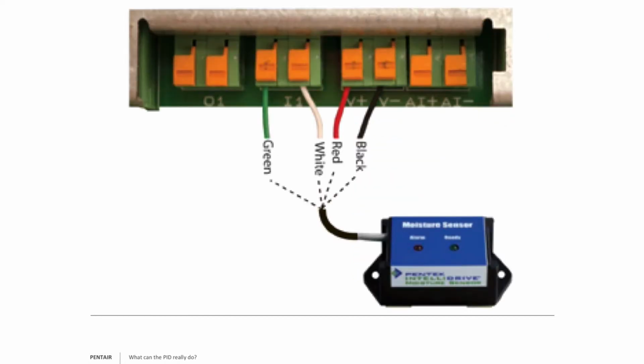Now this is a very typical one you'll see. This is our water detection device. One fair warning I want to tell you is that I told you we only have 20 milliamps on the board. The other 20 of the 40 is already used by our analog input, which is our transducer. So if you intend on trying to hook up more than one of the water sensors, you can't support it with our onboard power supply. It will do one, but it can't do 3, 4, or 5.